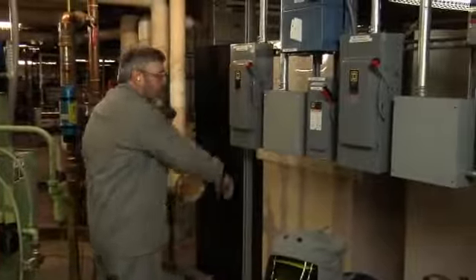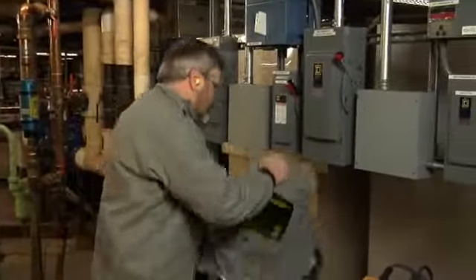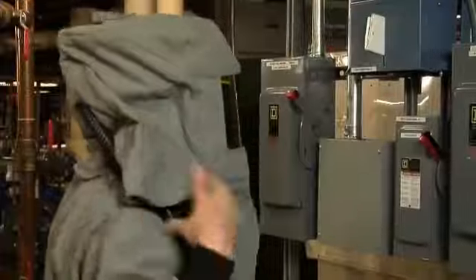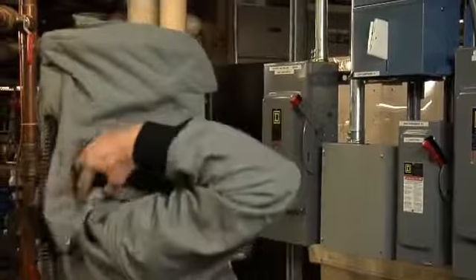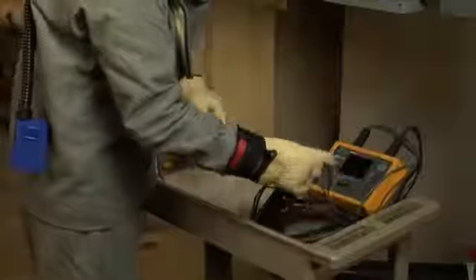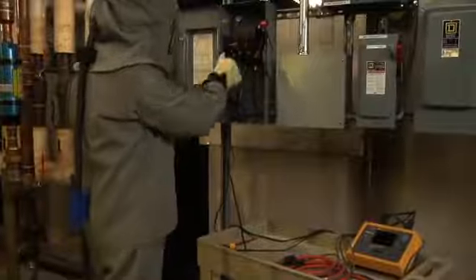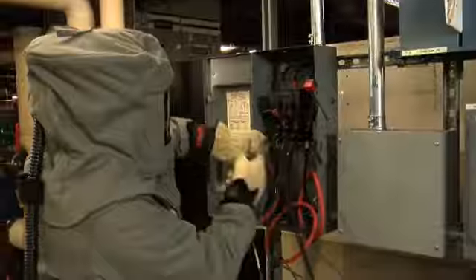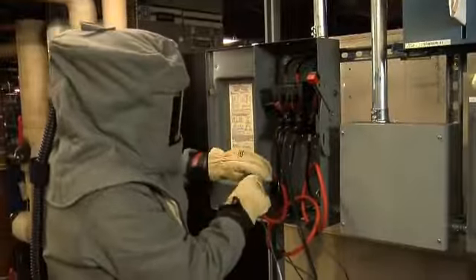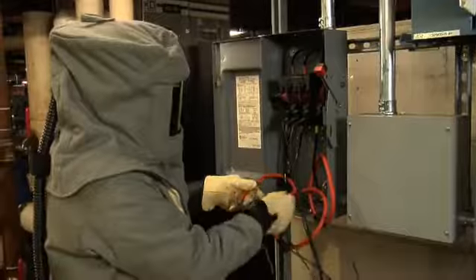Identify culprits and log power factor at those loads. Again, make sure you are wearing all proper PPE. That means selecting your PPE based on arc flash warning labels or NFPA 70E tables as appropriate. Always remember to follow safe work practices when opening and closing your doors. Prepare your power logger test leads and connect to the correlating connections. Then, connect the flexi loops to the matching connections, making sure that all connections are correctly made.